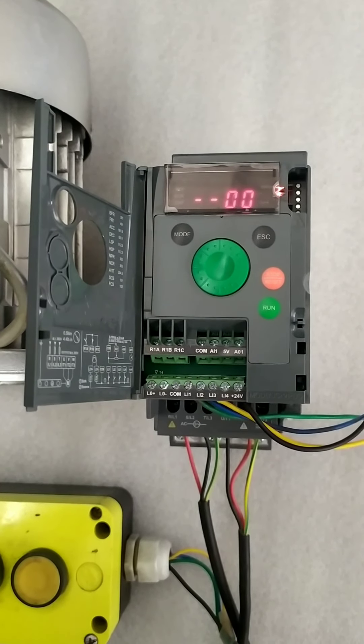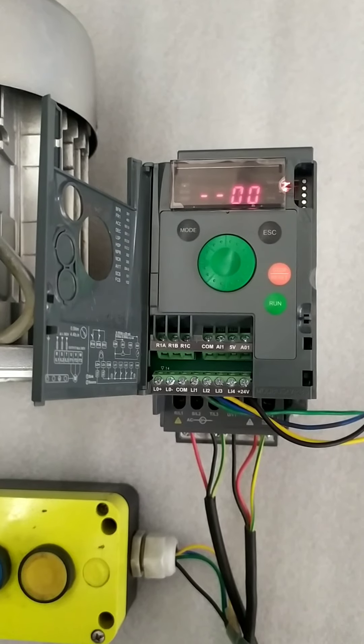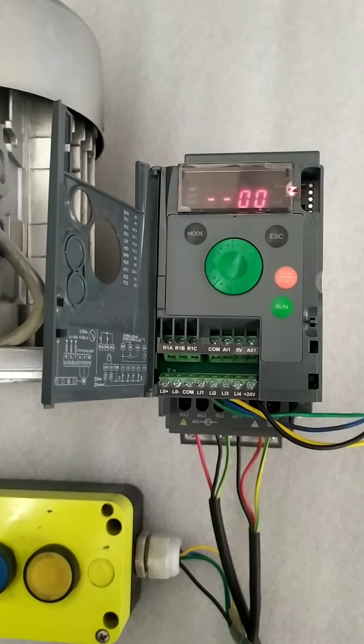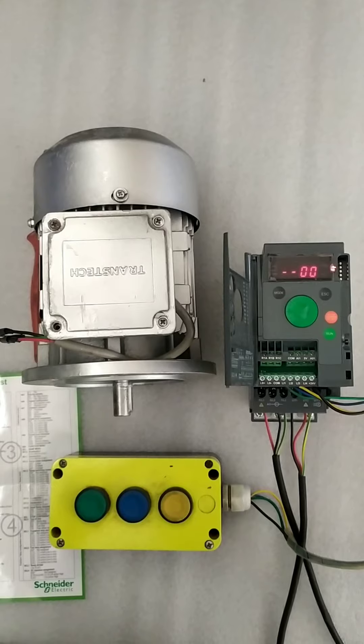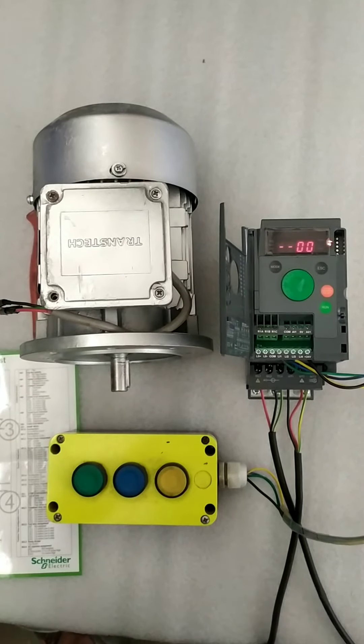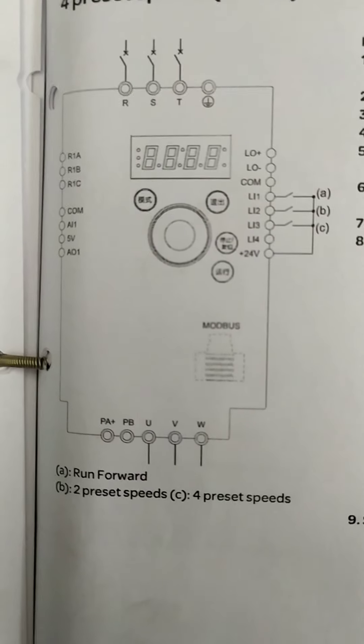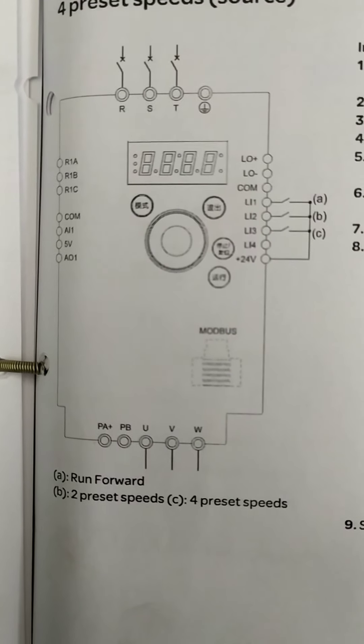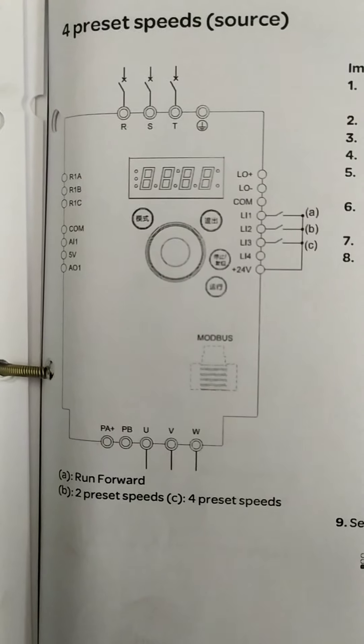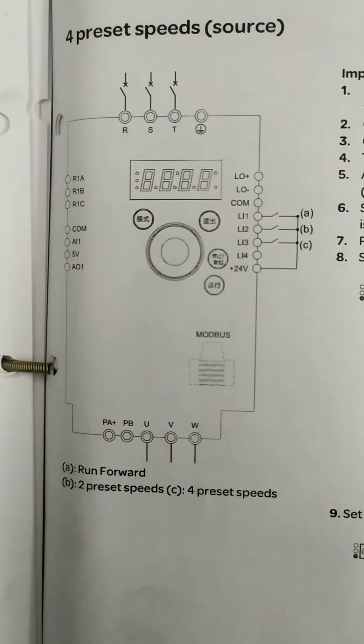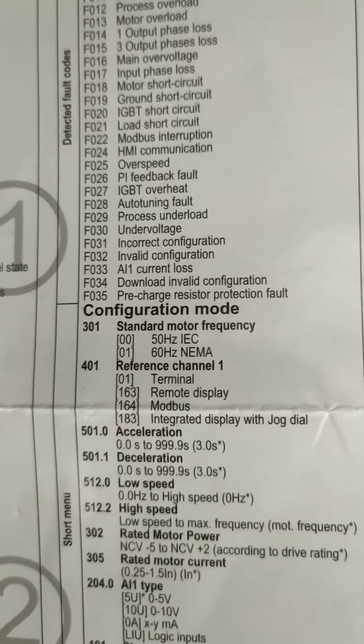We have set motor connection and push button input to the drive. To make 3 preset speeds, we make some arrangements with the motor and 3 push buttons for obtaining 3 speeds. We have taken command 24V for the 3 push buttons. For the first preset speed we have taken LI1, for second speed LI2, and for third speed LI3.